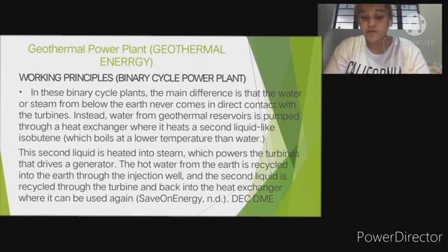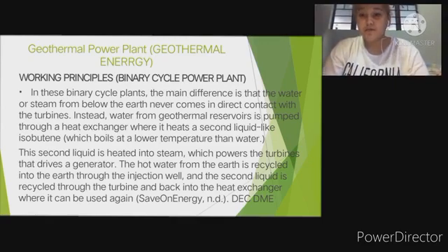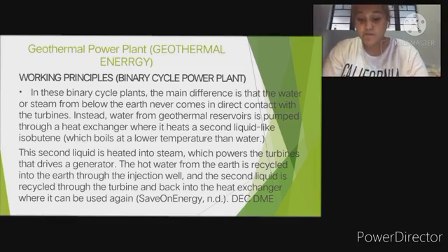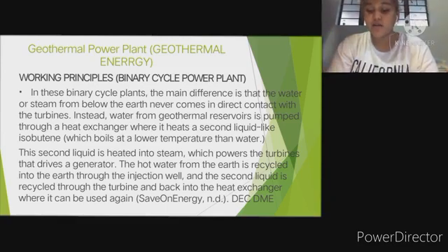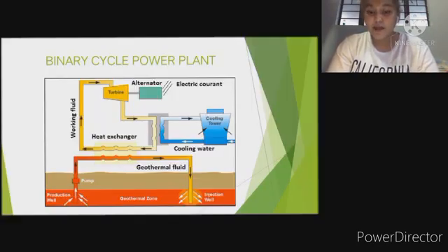Next is the working principle of the binary cycle power plant. In binary cycle plants, the main difference is that the water or steam from below the earth never comes in direct contact with the turbines. Instead, water from geothermal reservoirs is pumped through a heat exchanger where it meets a second liquid, like isobutane, which boils at a lower temperature than water. This second liquid is heated into steam, which powers the turbines that drive a generator. The hot water from the earth is recycled into the earth through the injection well, and the second liquid is recycled through the turbine and back into the heat exchanger where it can be used again. This is an example of a binary cycle power plant.